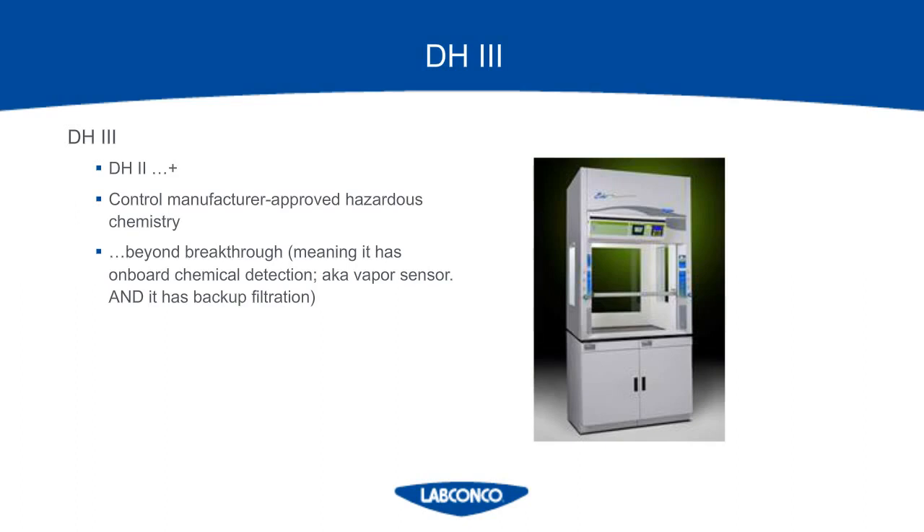Once the primary filter breakthrough point has been detected, a DH-3 ductless hood should be designed to provide a period of time to continue and end an ongoing experiment with its secondary backup filter system. The secondary filter must be of the same type of media and efficacy as the primary filter. These hoods typically have one universal carbon type that can filter out acid bases and solvents. At LabConco, the DH-3 products are called the Protector Echo and Protector Arrow — a marriage of products between LabConco and a company called Erlab using their green fume hood technology. We refer to these as filtered fume hoods to differentiate them from other ductless hoods.